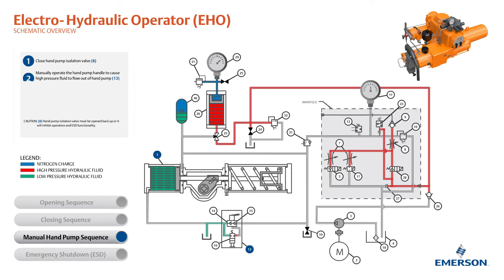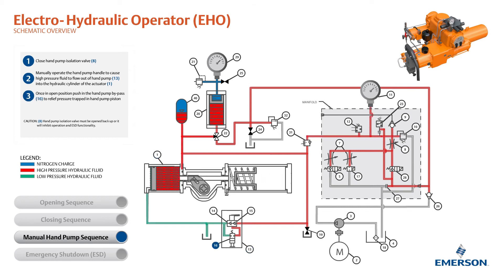Next, manually operate the hand pump handle to cause high-pressure fluid to flow out of the hand pump into the hydraulic cylinder of the actuator. Once in the open position, push in the hand pump bypass to relieve pressure trapped in the hand pump piston. The hand pump isolation valve must be opened back up or it will inhibit operation and ESD functionality.